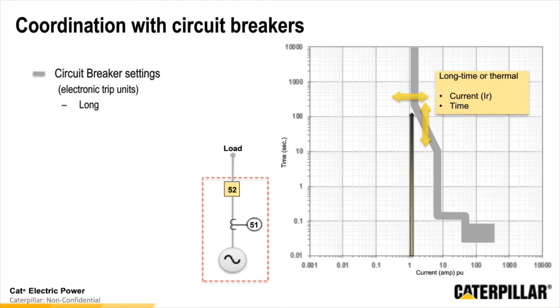So let's look at some of those settings that we might have. With the circuit breaker, the first section that we're going to look at is the long-time or thermal trip settings. Typically, it's considered thermal because there's a bimetal that's used, and it uses temperature over time to be the determination for the setting. But we're able to make those settings with both a current and a time threshold, so we can move that curve at the top portion left or right or vertically, to be able to set and align with the settings that we'll show as we go forward within the system.